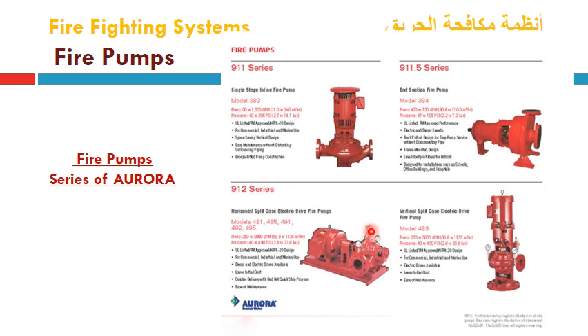and an automatic air release valve is connected here to the pump casing, and finally the end suction type with bare shaft without driver. We can connect a diesel engine or a horizontal electrical motor, and this is the suction flange of the pump, and this is the discharge flange of the pump, and the shaft is located this way horizontally, as discussed before in the detailed construction drawing presented earlier in this lecture.